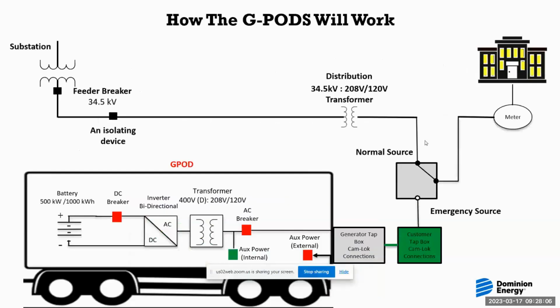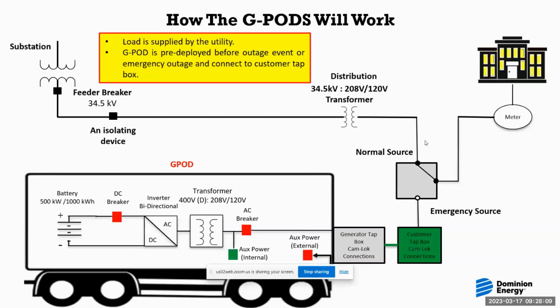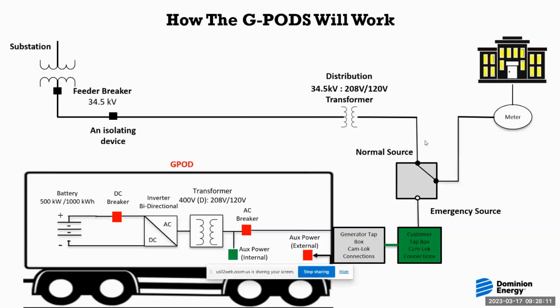So how will the GPODS work? You see a picture of the GPOD in the lower left-hand side - it's really the Hanover pilot project on a trailer. Starting on the left-hand side, we have the battery energy storage system. In this case, it's a 500 kilowatt, 1,000 kilowatt hour system, so I could do 500 kilowatts for 2 hours with this system. Then I have a DC breaker and the bidirectional inverter.